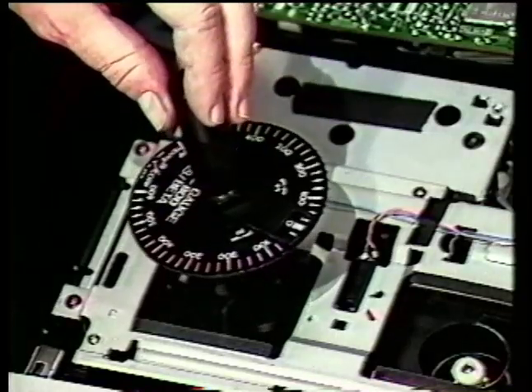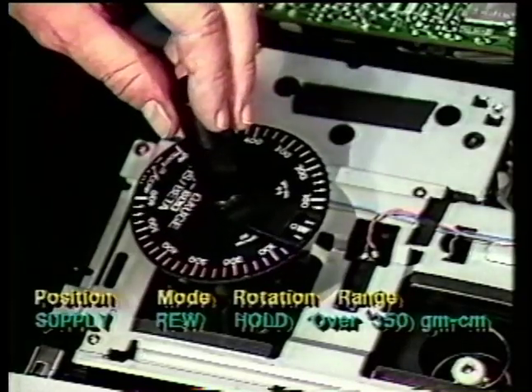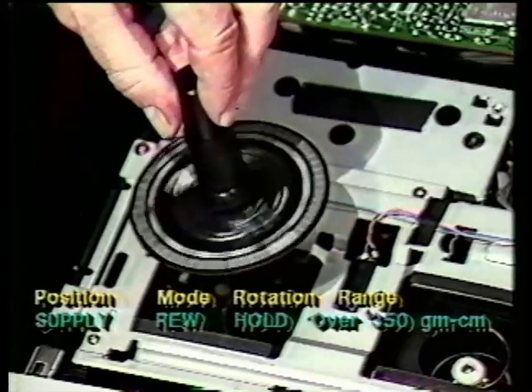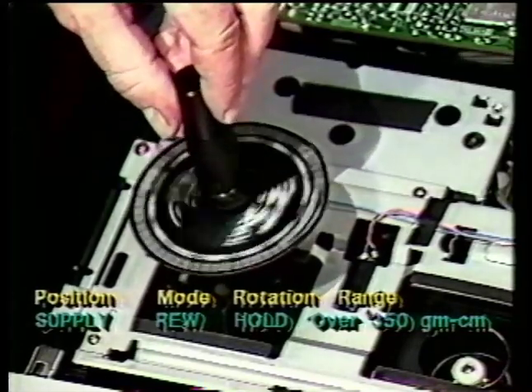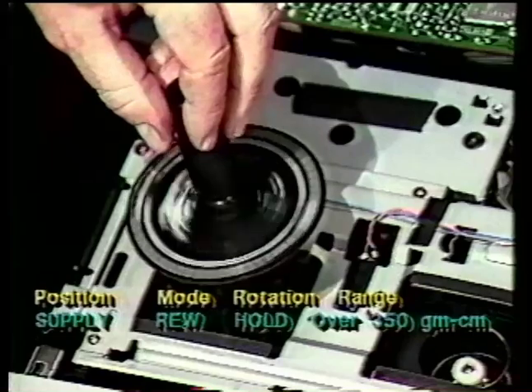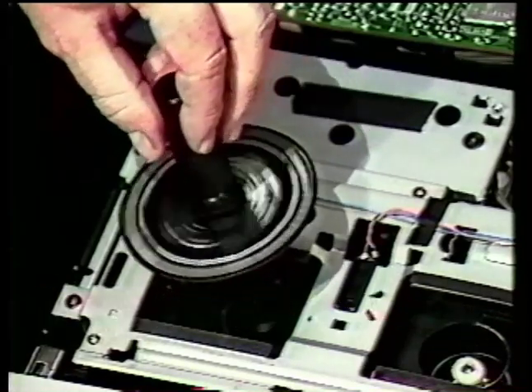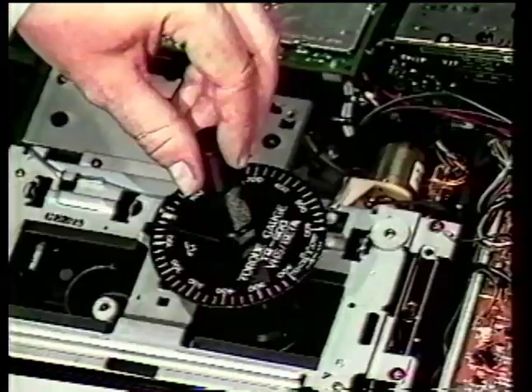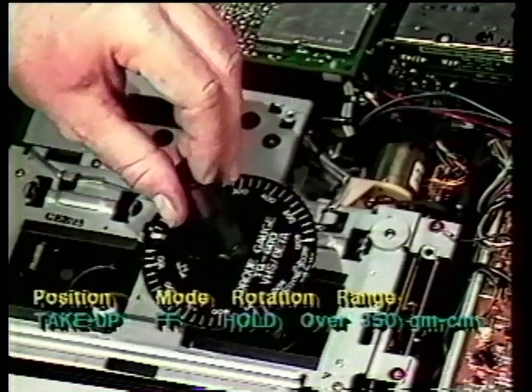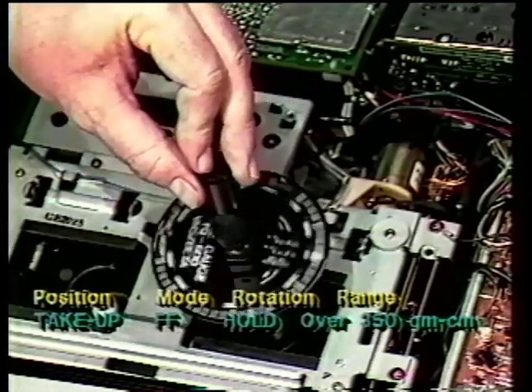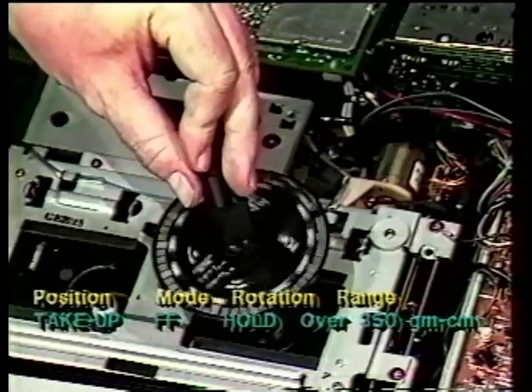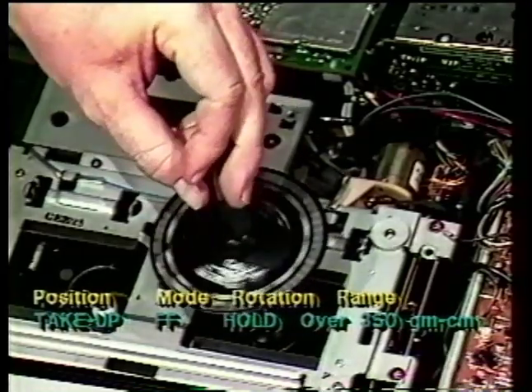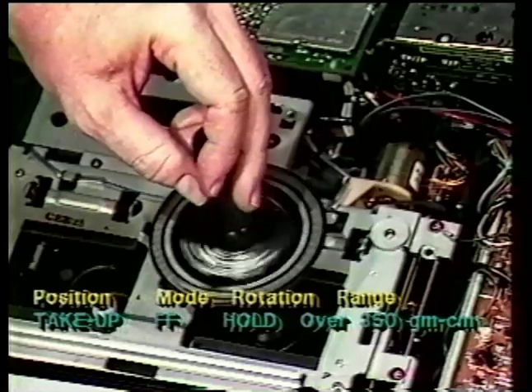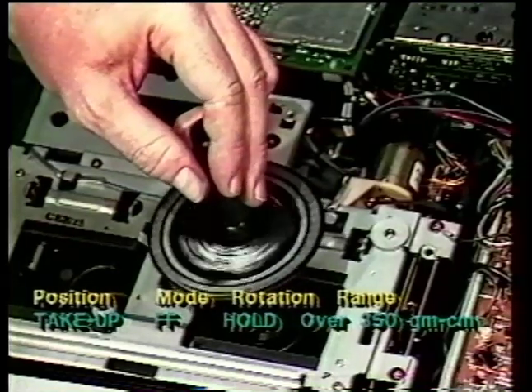On the supply reel, in the rewind mode, there should be plenty of torque to make sure that the tape gets pulled. You can see the torque gauge is definitely going over 600 gram centimeters on this machine. On the take-up spindle in the fast-forward mode, same reasoning applies. There should be lots of torque to drive the tape forward. And you can see that its brake is very good, or the clutch is very good on this machine.